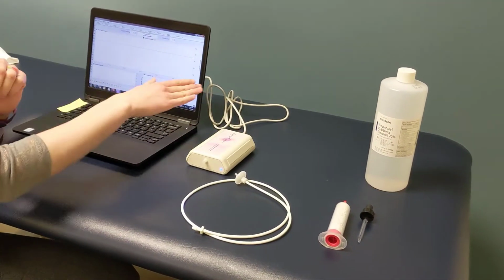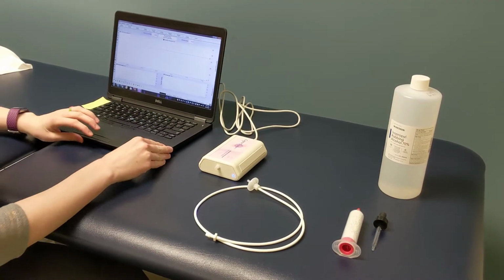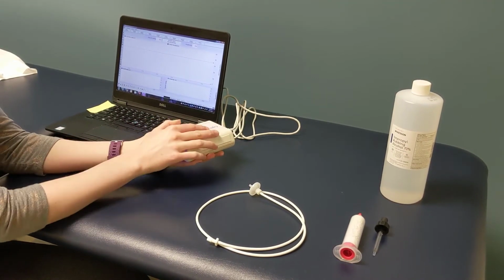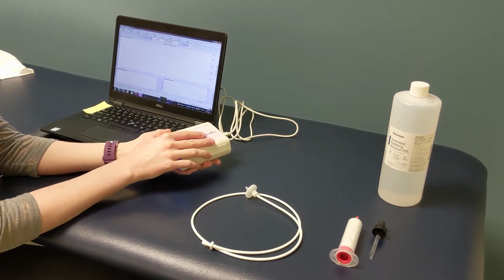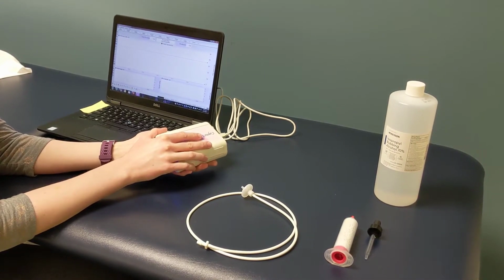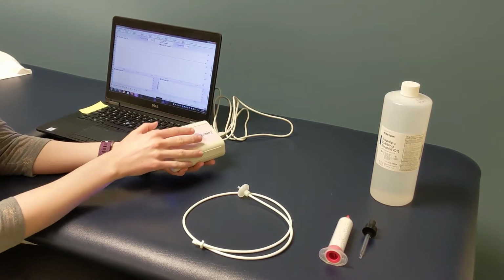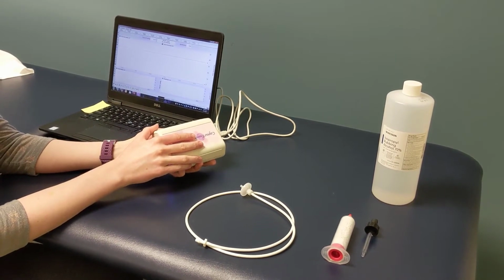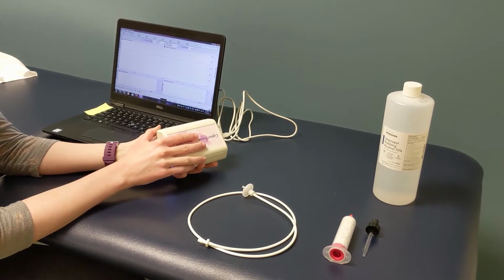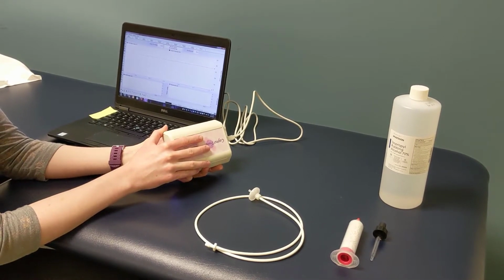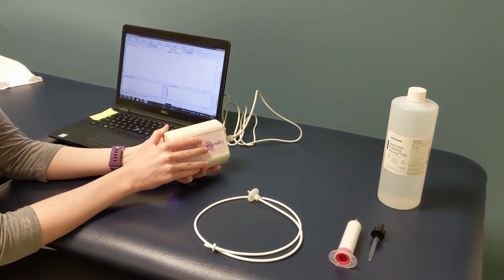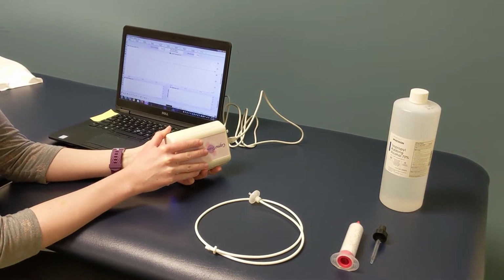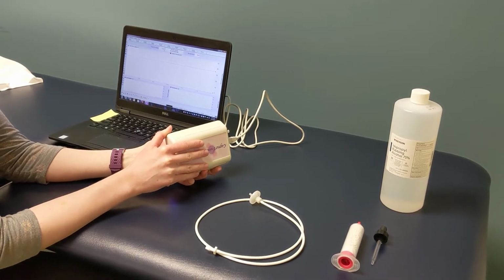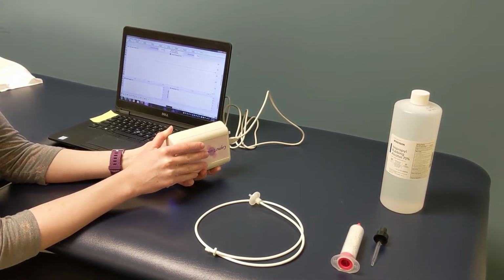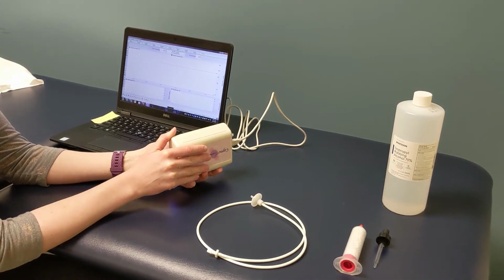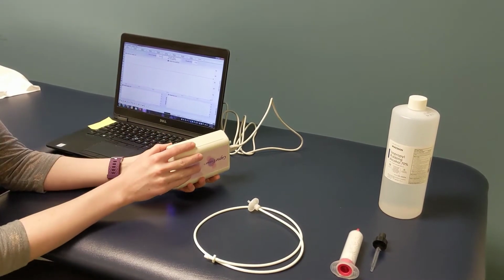And on the screen, if it's not a consistent line, you're going to hold the CapnoTrainer in your hand and very slowly rotate it back and forth. And that's going to let the air, it's a one-way valve, go through to get rid of any water. That's the thing about the CapnoTrainer. The great thing about it is that it's a one-way valve. However, it does make it a little harder to get any condensation out of there. So you very, very slowly turn it back and forth so it's all the way over 180 degrees. Then you just keep going back and forth until you have a consistent line on your screen.